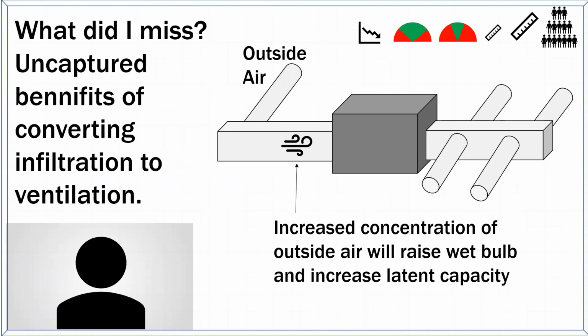So one of the things I did not capture with this analysis, by the way, I did not do manual S calculations on everything. That's a big deal because when you have outside air being drawn directly into the return air plenum, you have a higher concentration of moisture in that return air plenum. What does that do? It means the air you're blowing across the coil is more humid than it would be if you dumped it into the house through infiltration.